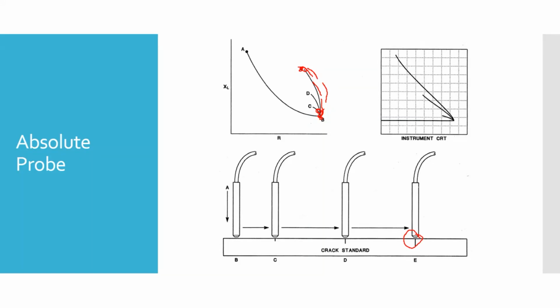Because if we keep going and go over an unknown crack or an unknown thing, if we get an indication that comes up and comes back down somewhere between D and E here - in my example, C was 10 thousandths, D was 20, E was 30 thousandths - if that's halfway between, you can say that crack is roughly 25 thousandths deep. It's more than the 20 thousandths D, less than the 30 thousandths E, so it's about halfway. It's probably about 25 thousandths of an inch deep.